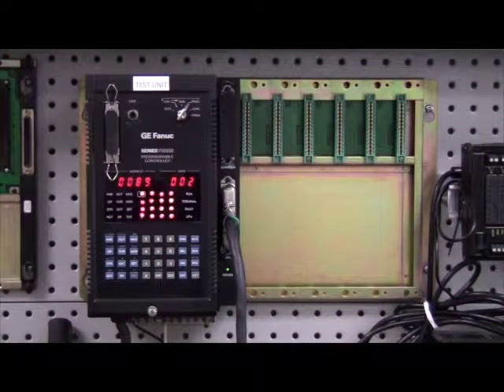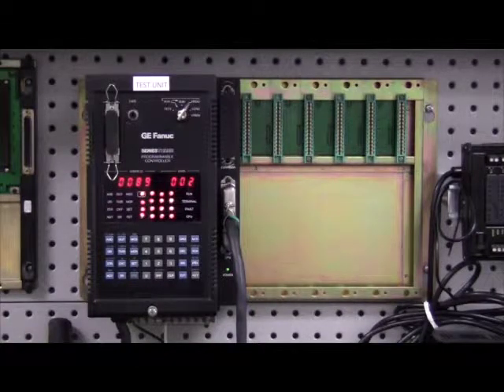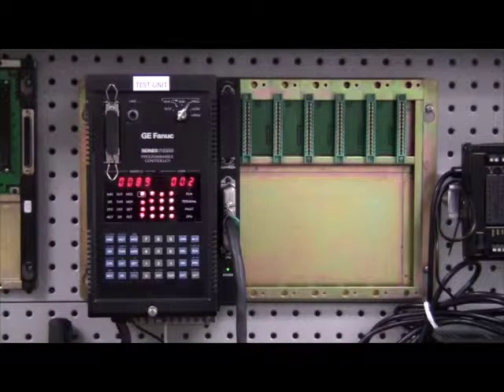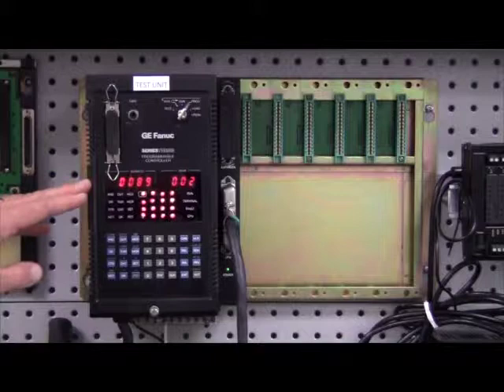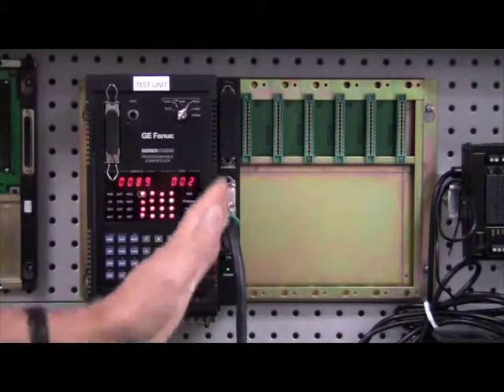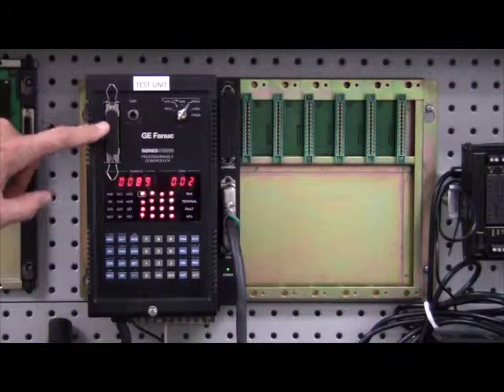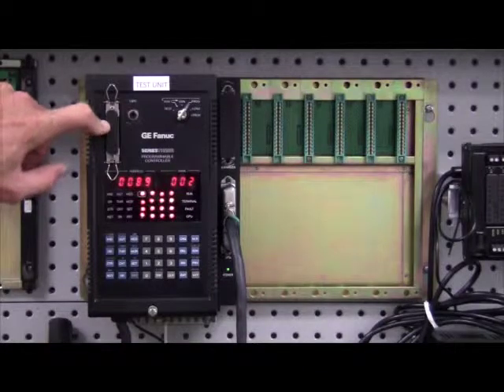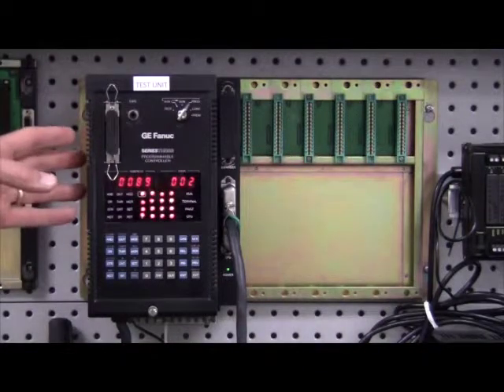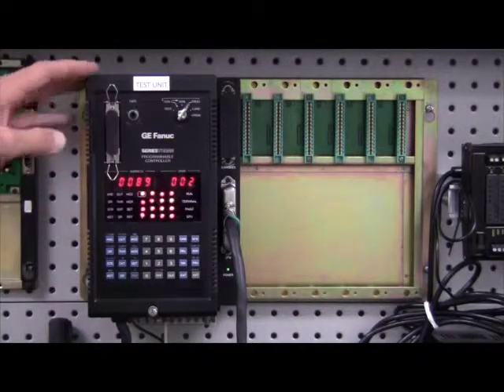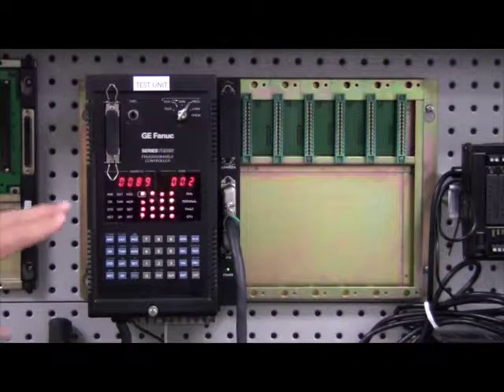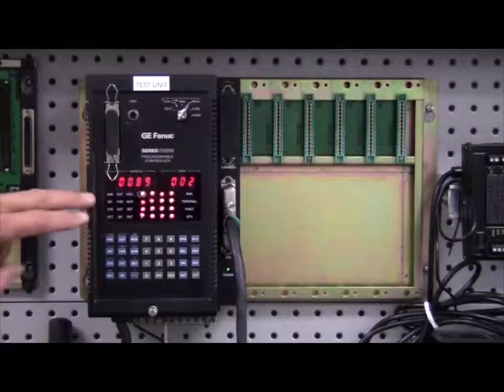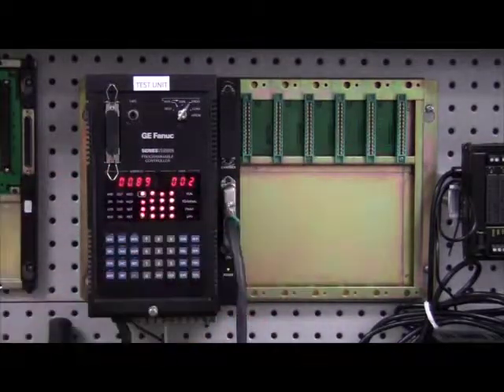The GE Fanuc Series 3 was the next PLC that was introduced after the Series 1. It's a mid-sized PLC and what's unique about this PLC is the programmer and the CPU are all one unit. The power supply remains behind it and the I/O cards to the right. It has a serial interface for Logic Master 3 software to be put for programming. It had a short life of about three years in the marketplace before the Series 5 was introduced and you will find these on elevators and grain mills primarily. We are able to repair these CPUs. Typically you're going to find some capacitors that decay and fail on them as well as all the I/O modules.